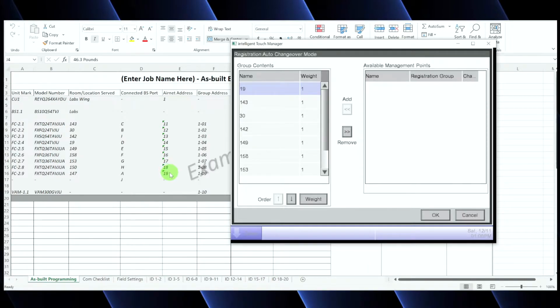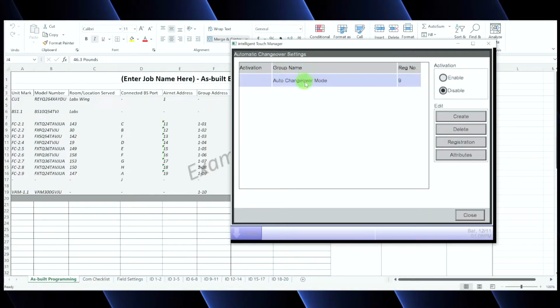One kind of workaround is by giving all these units a different weighted value. And when you give them a weighted value, they basically have a bigger say in what mode they want. So if you add up all the units that are calling for heat and the value is 4, and then you add up all the units calling for cooling and the value is 7, the bigger value is cooling, so the system switches over to cooling. And that's what the weighted value would do in the most basic explanation. We're not going to be playing with that in today's video. We're going to go ahead and click OK. So now we have our auto changeover group created with 9 indoor units, and at this point we can go ahead and click on enable.